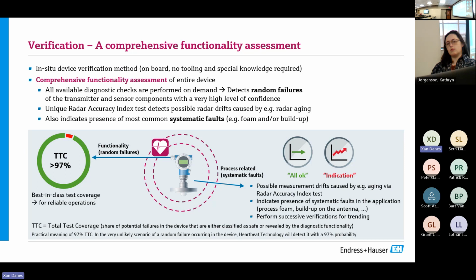That could be we put the radar on the acetone tank and right out of the box we're getting no signal back. How can we find not just random hardware failures with a high degree of certainty, which are particularly dangerous, but also find process-related systematic faults? That could be anything from buildup on the face, or it could be I installed this in a tank that had some alcohol-based solvent for 8 years, and after 8 years we decided to put acetone in that tank instead. So these are both faults that occur inside the device, but also outside of the device.